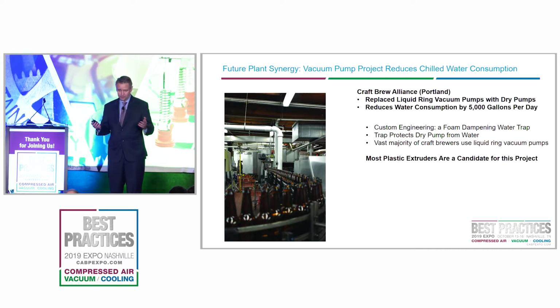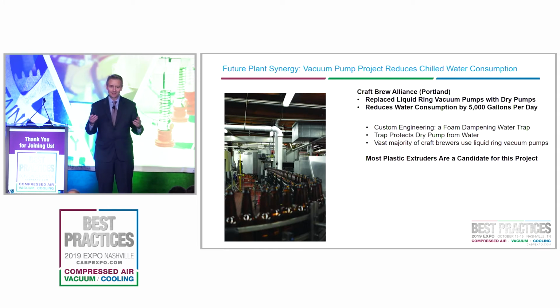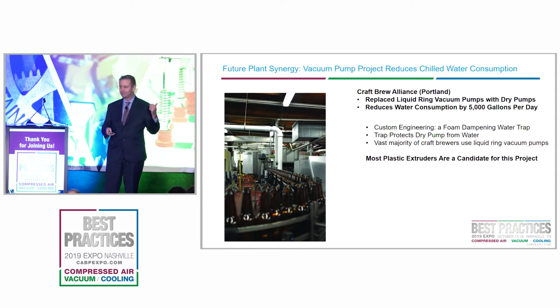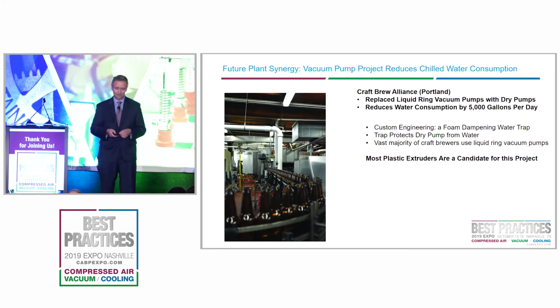We had a presentation yesterday from Solberg, and we've had presentations with case studies, but basically by using a special separator, a special water trap which can block the liquid from getting to the vacuum pump, you can go to a dry vacuum pump. It's hard to get the engineering hours from people because those aren't big pumps - people don't make a lot of money selling them. But we've got to raise awareness and let end users know almost every craft brewer in the country is a candidate for this. I would guess most plastic extruders are candidates too.